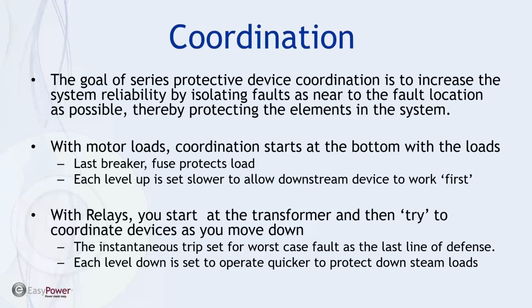So that means with motor loads, we're going to start coordinating with the last breaker or fuse being adjusted specifically for protection of the particular load. And then we have to slow down, if you will, or set upstream devices sequentially slower. And so in the overall scheme of things, the top relay, which will be the last protective device in the series, has to be slowed way down to be coordinated.